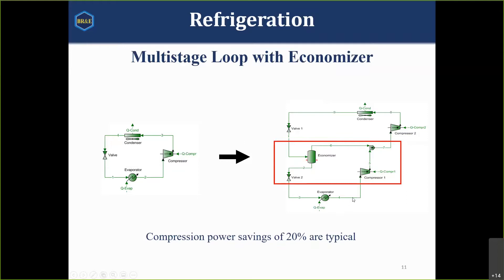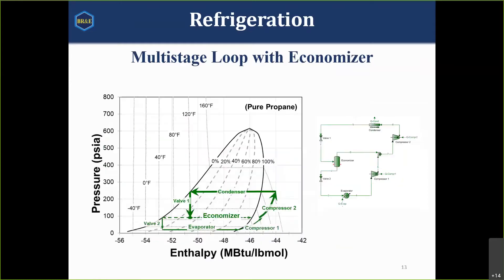This gives us two benefits: a larger liquid fraction going into the evaporator, and a lower overall mass flow to compress from the lowest pressure back to the highest. We have a compressor taking the lowest-pressure refrigerant back up to the intermediate economizer pressure, then all refrigerant is mixed and boosted back to the final condenser pressure. On the pressure-enthalpy diagram, stream three represents the bottom corner — we're starting with a larger fraction of liquid going into the evaporator, and still compressing up to about 240 psia.